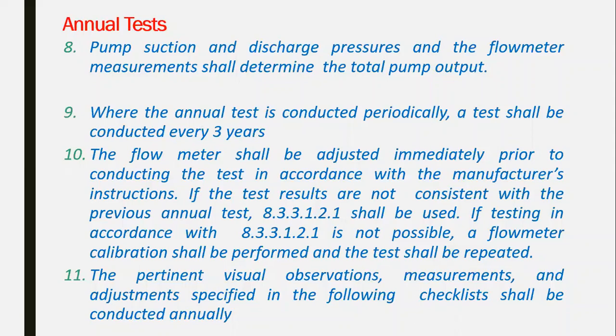What are we going to do with all of these tests, the weekly inspection, the monthly running of the pump, and annually? Why are we making all of these tests? Is it important to run it? We are saying to take a record for the pressure, the flow, the voltage operation, the oil pressure, the battery charging, and the current and volt. We are taking a lot of readings for each one. What will we do with all of these readings and records? Are they recorded somewhere?